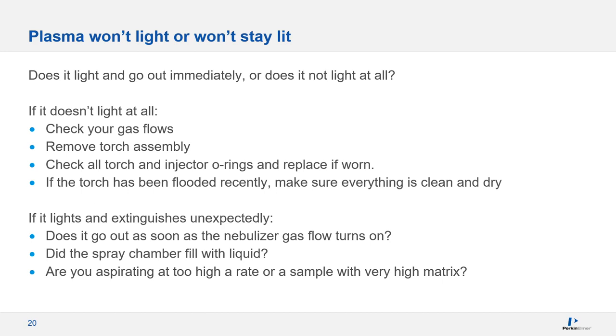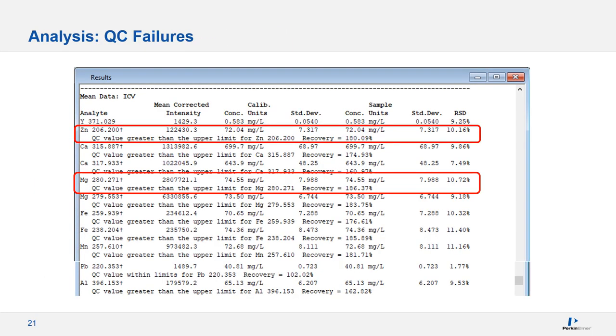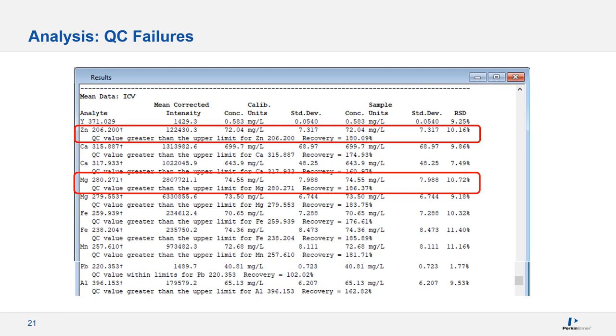So let's move on and discuss some issues your data might indicate. You've done all your maintenance and started your run, but there's a problem. The QC fails or your results are just not what you expected them to be. A QC failure is often what triggers a call that the instrument isn't working. But keep in mind, if your instrument has similar intensities as it had in the past for the same solutions, such as your standards, it's not broken. If you can build a calibration curve for all or even just some elements, that indicates there's a problem with chemistry, sample introduction, method, peak or background positions, that kind of thing. This is when having good troubleshooting skills can really help.